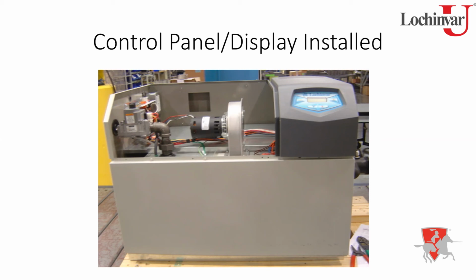Now, like I said, once it gets on the job site, it travels across the country in the back of a truck somewhere. It gets on the job site, you stick 40 feet of vent pipe on it. Oh, yeah, absolutely. Things are going to change a little bit. That's why you've got to go in and measure, make sure that the air is set correctly and your manifold pressure is set correctly, because they're probably going to change just a little bit from what we had at the factory. Right. So just come prepared when you are going to do a startup. You may have to have a manometer to check some pressures and slightly adjust them. Yep. Just remember, air pressure first, and then your net gas, in that order.